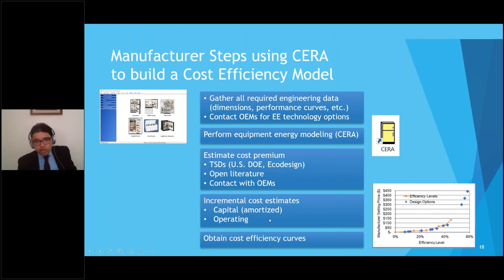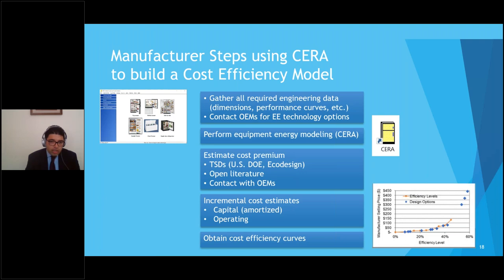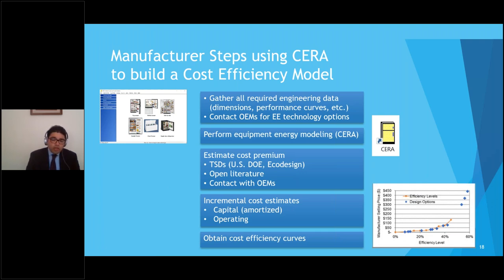In terms of incremental cost estimates, we differentiate capital costs and operating costs. For example, modifying thermal insulation thickness requires creating new injection molds and changing the metal cabinet siding — a significant capital cost that must be amortized. For foam insulation, operating costs include using more foam material. Moving from HFC-134A to isobutane involves capital costs for safety equipment and charging machines, but also operating cost savings on refrigerant, offset by needing more trained technicians and higher insurance premiums. These factors all need to be accounted for.